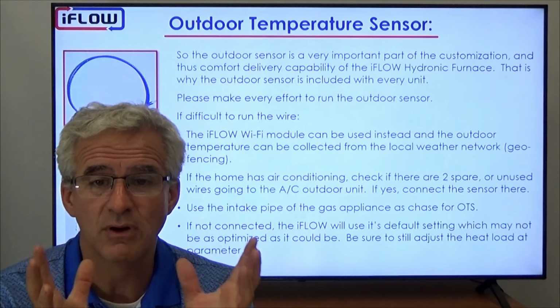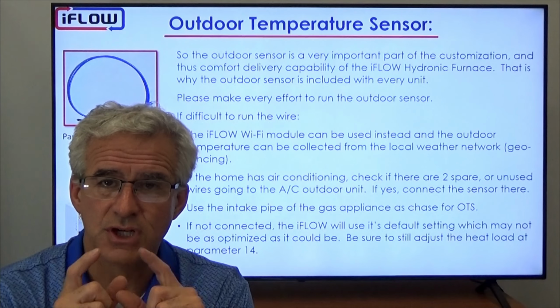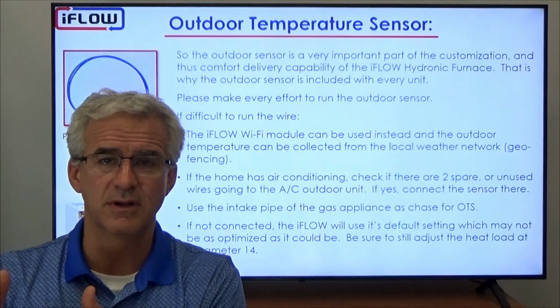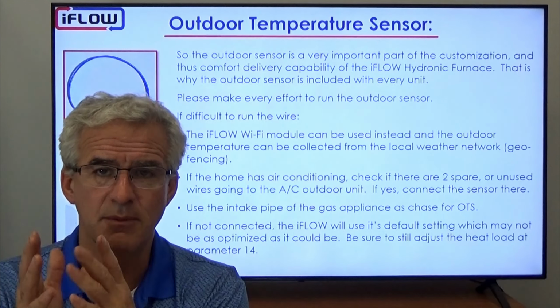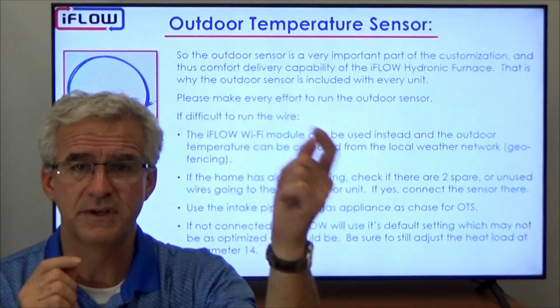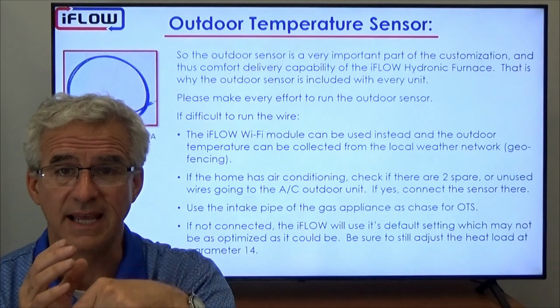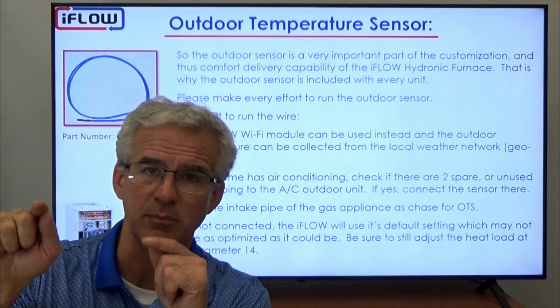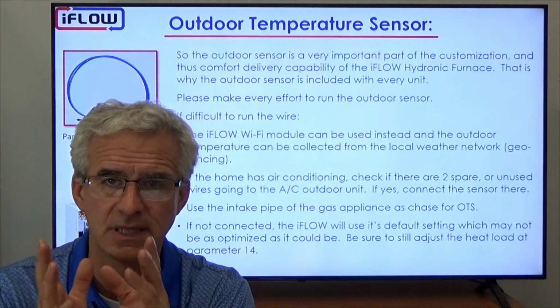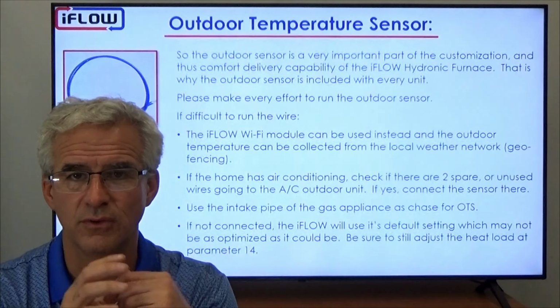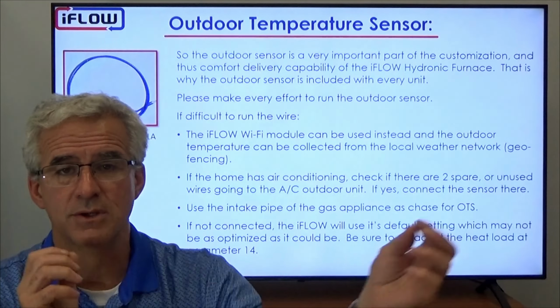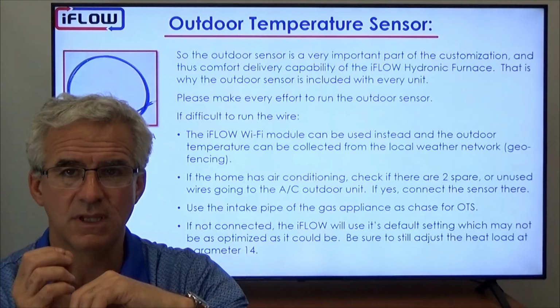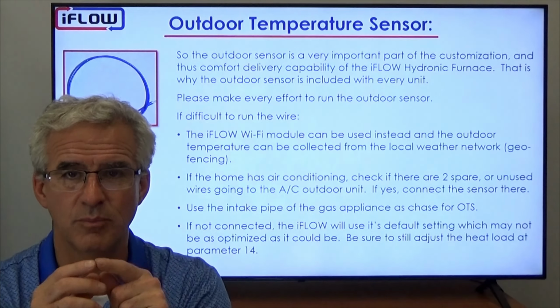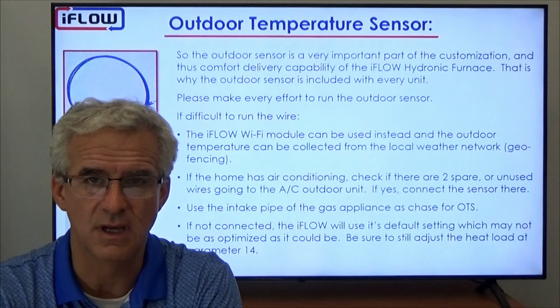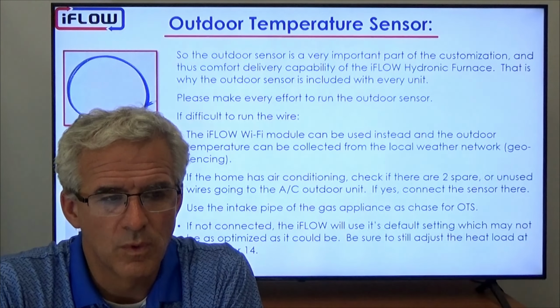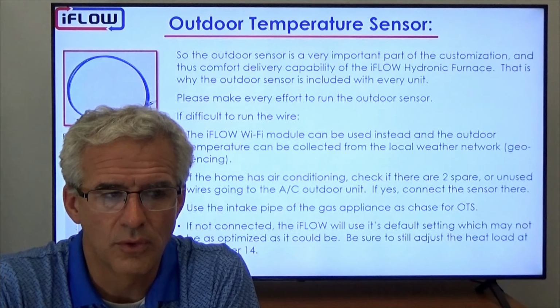If you don't have a spot, or if it's difficult, remember you can always use the chase of the appliance. If you have a direct vent appliance where you've got an intake pipe, you can use the intake pipe as a chase for the wire. So just fish it back through the intake. Do not do it on the exhaust. Of course, we don't want any hole penetration through the exhaust pipe. It's only through the intake where it's bringing air in. Running the wire through there is not going to restrict any airflow at all. So fish the wire back from the outside down through the intake pipe, and then bring it out through the intake pipe. Just run a little pilot hole, draw it through, connect it to the iFLOW. So that's another way you can get it out without having to run a new hole through the exterior.